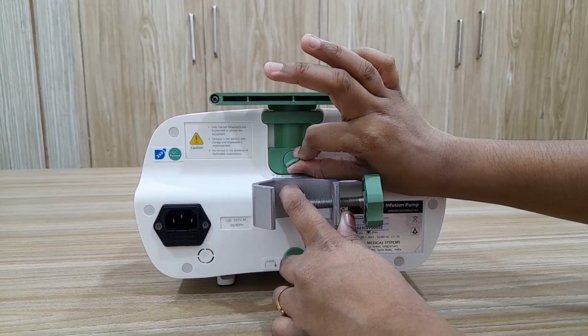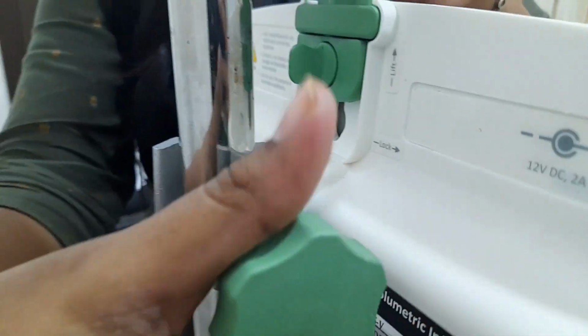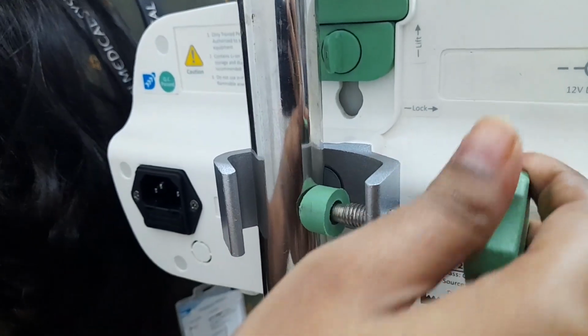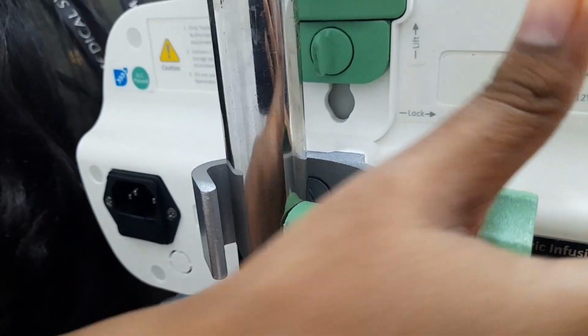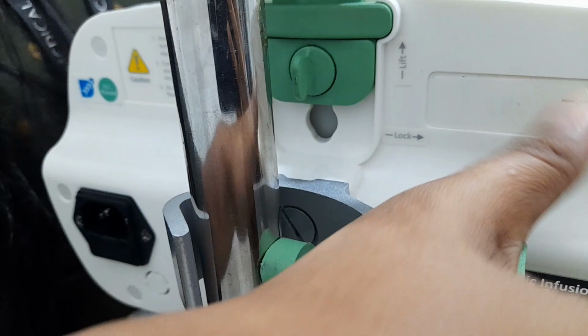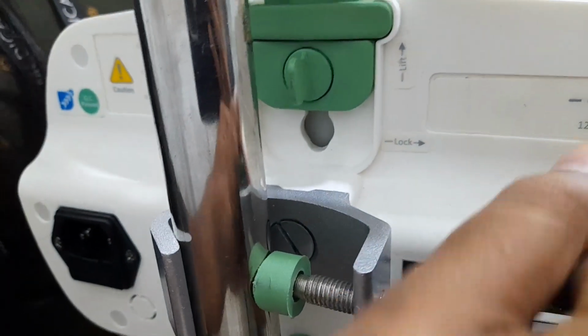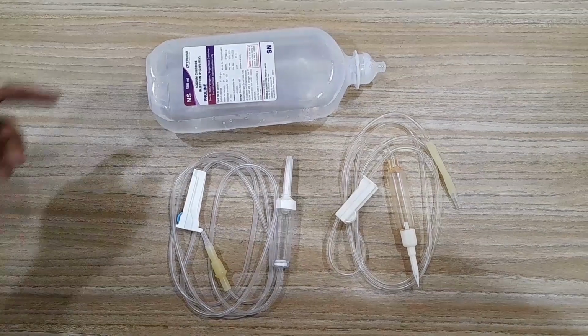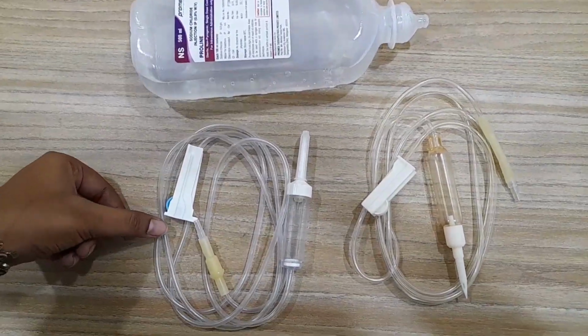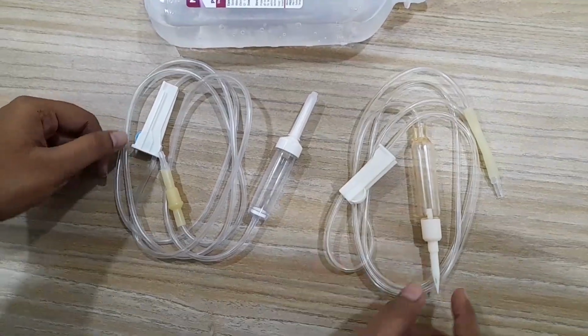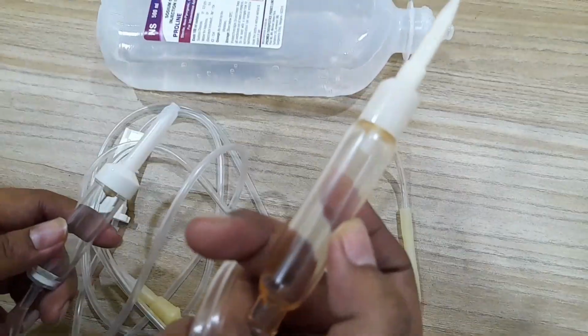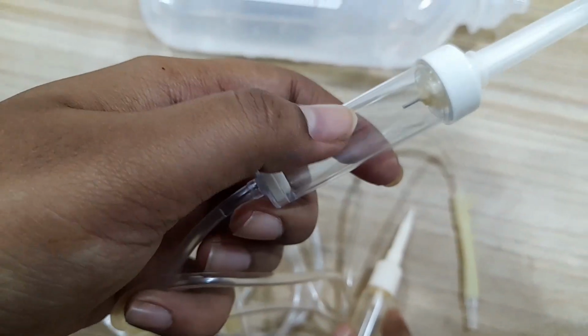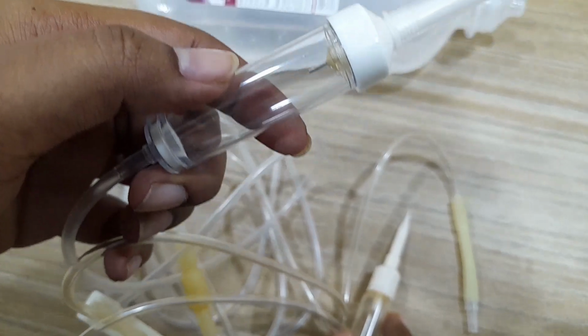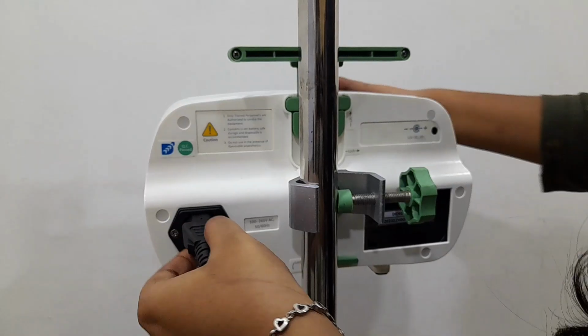Now we can see how to fix the Infusys V securely on the pole stand using the pole clamp. As said before, provision is given to fix the unit in horizontal or vertical pole clamp. Based on the requirements, loosen the IV block screw to adjust it for horizontal or vertical position. Here we adjust it for horizontal position using the IV knob and IV knob cap. Here we can see the IV bottle and two types of IV sets, micro IV set and adult IV set. In our product, we can use both micro as well as adult IV set. You can differentiate them by the small needle present in the micro IV set, whereas the adult IV set has a larger opening. Micro IV set is mainly used for neonatal and pediatric patients.